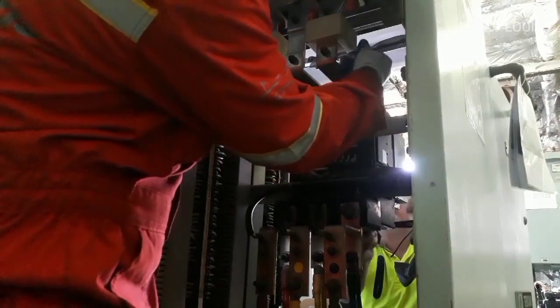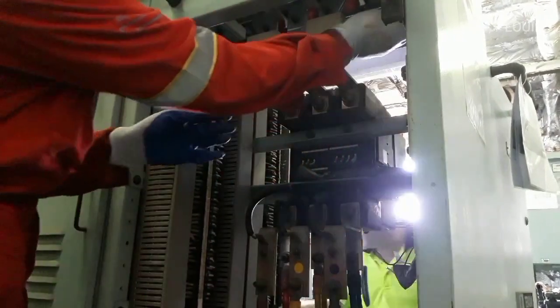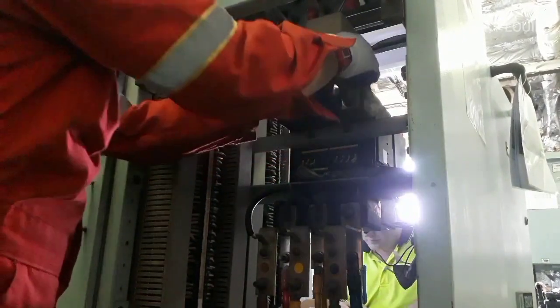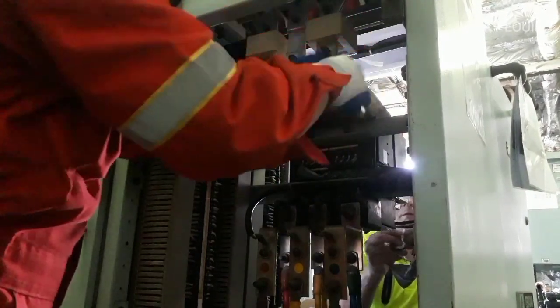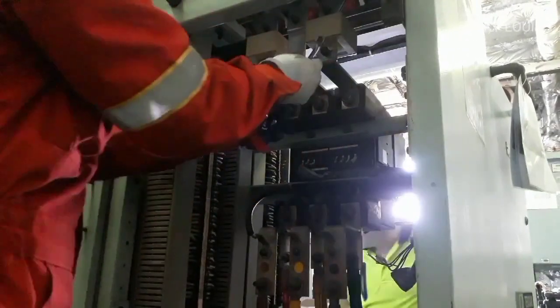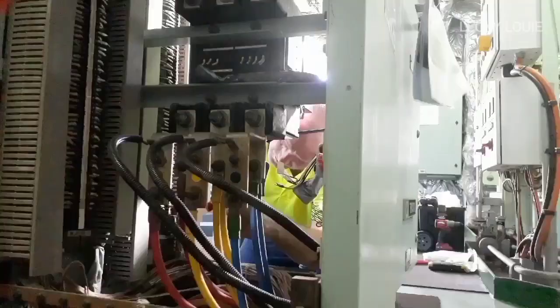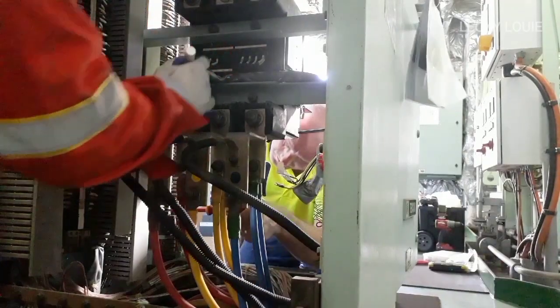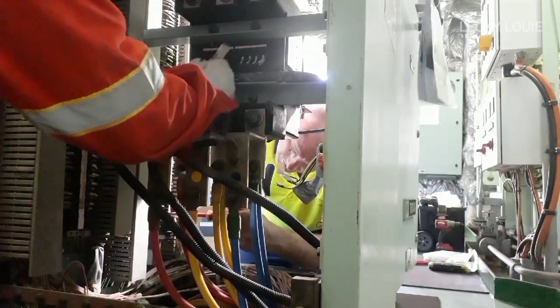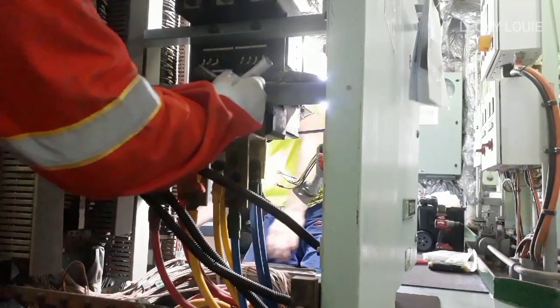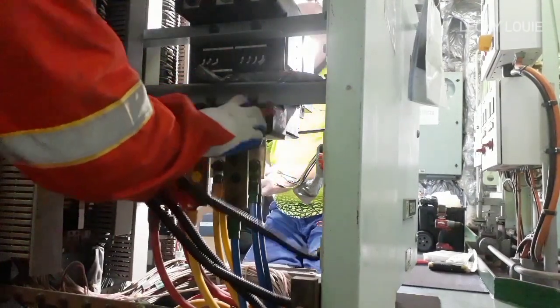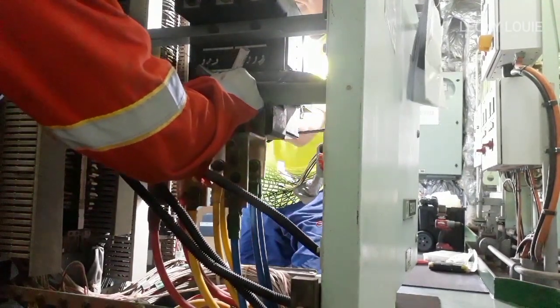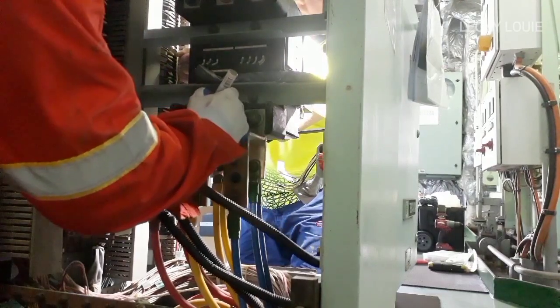The existing circuit breaker is an old type and we cannot find any supplier for this kind, so they decided to replace it with a Schneider brand. It has a different dimension but with the same ampere rating or capacity. But since this is a different kind and brand, we need to do some modification on how to fix it inside the switchboard, and also modify the electrical connections or wirings.